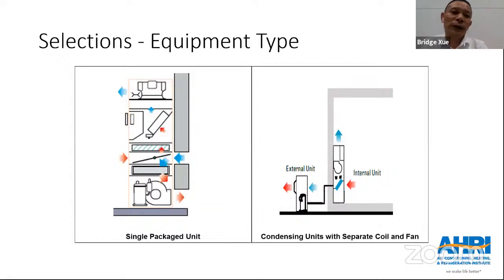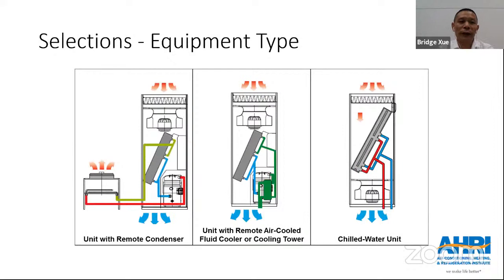So for this slide, this is just to let you know how many equipment types will be applied. The first one, on the left side, is the single package unit, and the other is the separate unit, including indoor and outdoor unit. This slide shows the other three. The first is a unit with remote condenser unit, and the other is a unit with a remote air-cooled fluid cooler or cooling tower. Maybe the cooling will be from a cooling tower. The last one is the chilled water unit. We call this the large room fan coil unit, which will be applied for the data center.